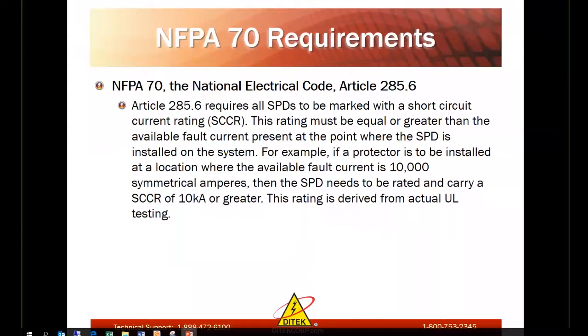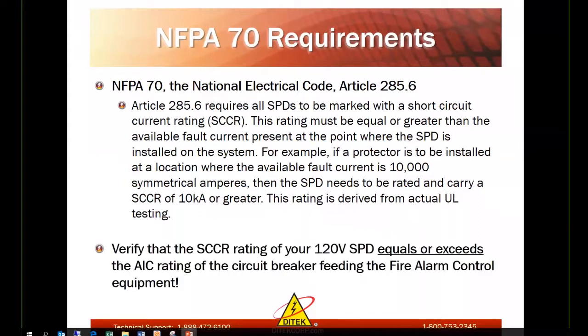This rating must be equal to or greater than the available fault current present at the point where the SPD is installed on the system. For example, if the protector is to be installed at a location where the available fault current is 10,000 symmetrical amperes, then the SPD needs to carry an SCCR of 10 kA or greater. This rating is derived from actual UL testing. Verify that the SCCR rating of your 120-volt surge protection device equals or exceeds the AIC rating of the circuit breaker feeding the fire alarm panel.